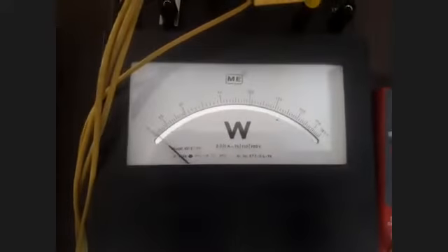So it will take a minimum amount of power, or a small power, because power is required only to overcome the no load losses. That is, P input at no load condition is nothing but the no load losses of the machine. That is P_i, the iron loss, or we can call it the core losses of the transformer.